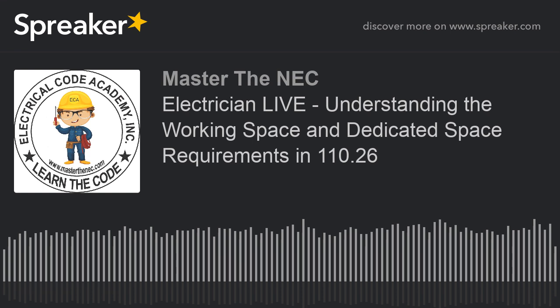So if I'm going to have a vault that's going to have low voltage and over 1,000 volts in the same location, then I have to construct a way to separate the high voltage equipment, effectively separating it with partitions, fences, or screens away from the lower voltage applications, okay, 1,000 volts or less. So I have to do that. And again, if you're in that world and you're dealing with vault rooms or some large enclosures, then you know that the separation is going to be inherent. And there's a lot of equipment that does have higher voltage coming into the equipment and low voltage going out, and it is separated by partitions that are built into the equipment that is effectively going to separate or partition off the high voltage application from the lower voltage application.